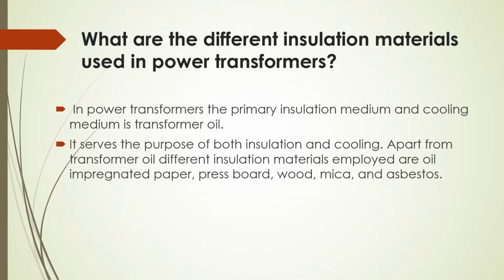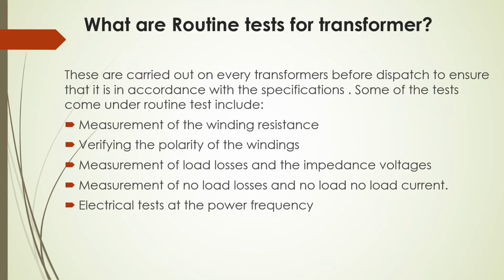What are the different insulation materials used in power transformers? In power transformers, the primary insulation medium and cooling medium is the transformer oil. It serves the purpose of both insulation and cooling. Apart from the transformer oil, the different insulation materials employed are oil impregnated paper, pressboard, wood, mica, and asbestos.